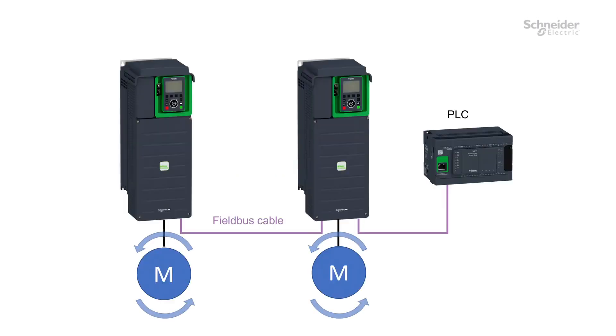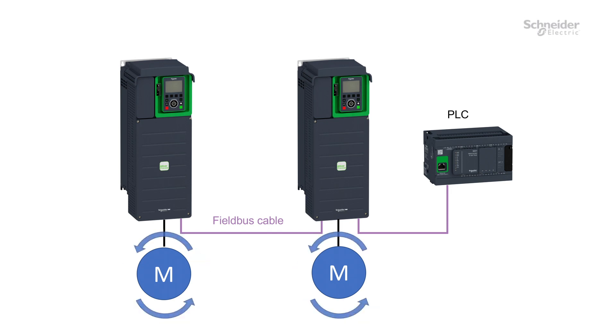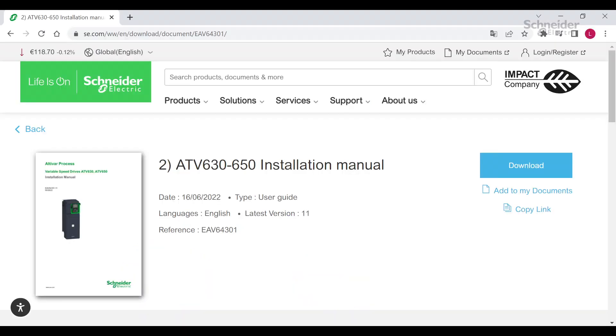If a communication error is triggered only when at least one motor is running, it may be an EMC disturbance. You must check that the wiring rules are followed. These wiring rules are provided with details in the installation manual of the ATV600.